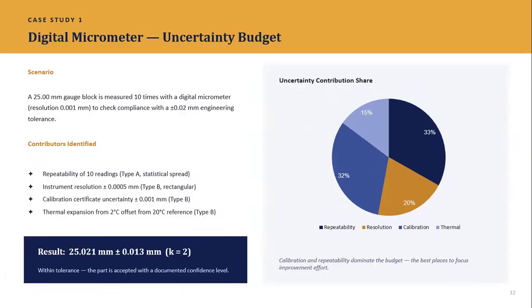Let us apply these basic concepts to a practical engineering example. Consider the case study of a digital micrometer. A 25 millimeter gauge block was measured 10 times using a digital micrometer with a resolution of 0.001 mm. The purpose is to verify compliance with an engineering tolerance of plus or minus 0.02 mm. The uncertainty budget considers several contributors. These include the repeatability of the 10 measurements, the instrument resolution, the calibration certificate uncertainty, and thermal expansion caused by a temperature difference from the reference condition.